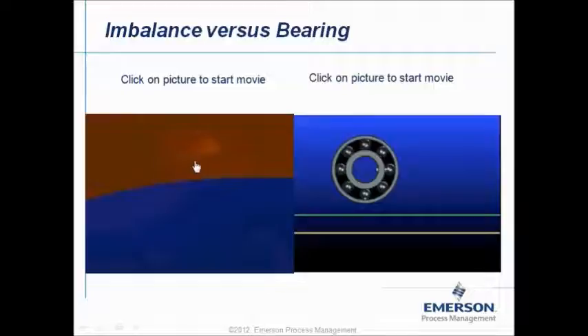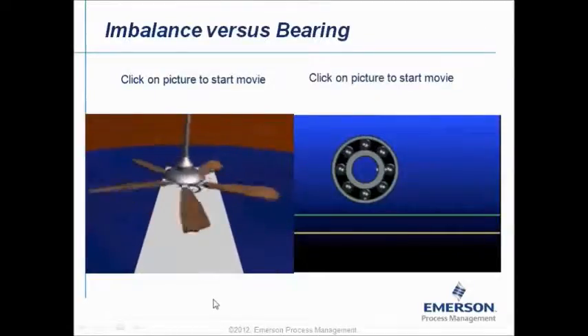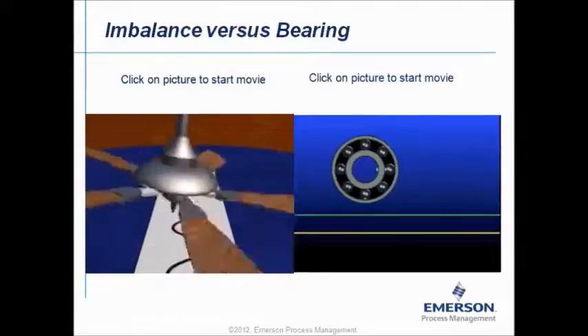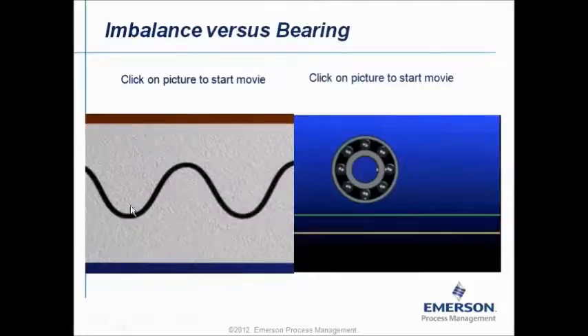On the left side you will see an animation of an imbalance. An imbalance, you can understand as a rotating wheel, but because the wheel is not perfect, on one side of the wheel you have a little bit more mass than on the other side. Now, if this kind of wheel starts rotating, it will create a vibration signal like this. It will create a perfect sinus, and from one minimum till the other minimum you have exactly one revolution, so one rotation of the shaft. That means in reality a typical motor is running 1500 revolutions per minute in Europe or 1800 revolutions per minute in America. Then if it has an imbalance problem, you will have 1500 or 1800 cycles like that in 1 minute of time.